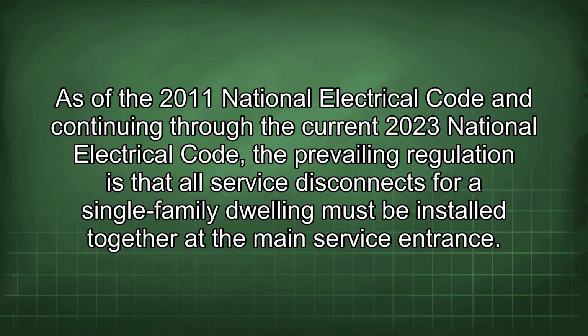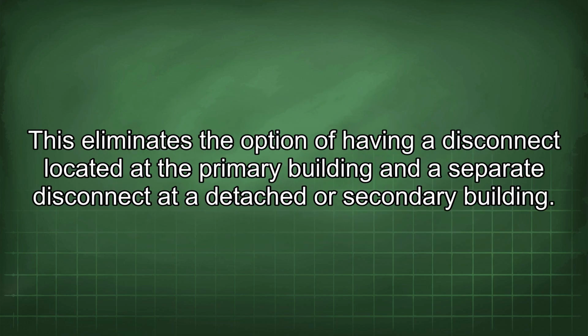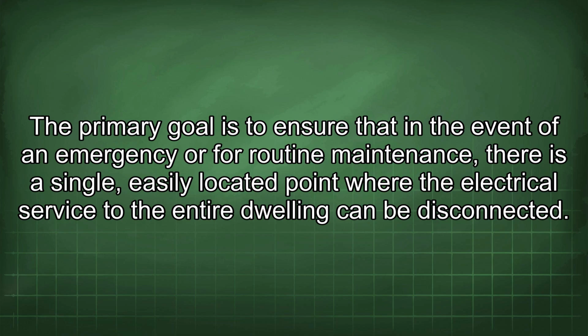As of the 2011 National Electrical Code and continuing through the current 2023 National Electrical Code, the prevailing regulation is that all service disconnects for a single-family dwelling must be installed together at the main service entrance. This eliminates the option of having a disconnect located at the primary building and a separate disconnect at a detached or secondary building. The primary goal is to ensure that in the event of an emergency or for routine maintenance, there is a single, easily located point where the electrical service to the entire dwelling can be disconnected.